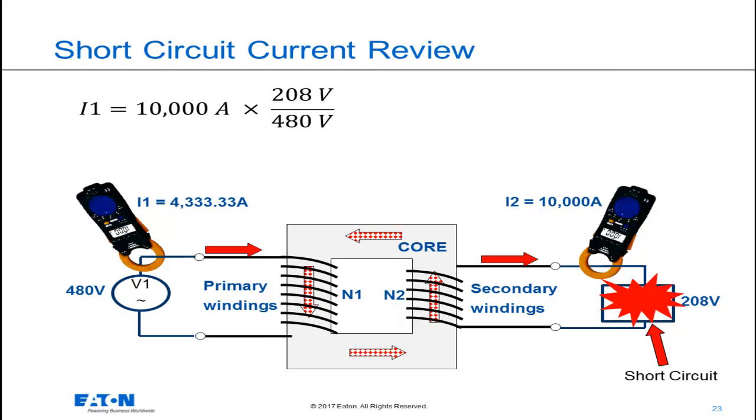So let's do an example to help us understand this. For this 480 volt to 208 volt transformer, should a fault occur on the secondary and measured by a meter to be 10,000 amps, an ammeter if placed in the primary would read 4,333 amps. That's calculated in the equation at the top of this slide. Thanks to the turns ratio of the transformer, the current on the primary is reduced because it's at a higher voltage.